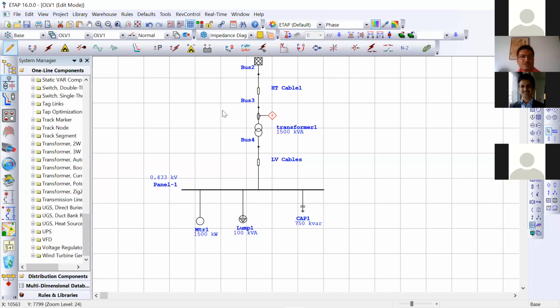And as you have seen, many more modules are available. Fast decoupled load flow analysis and transient studies can also be done. Say in this case, what will be the transient voltage drop if a motor suddenly drops because of some trip? Then what will be the over voltage condition in the system, right?